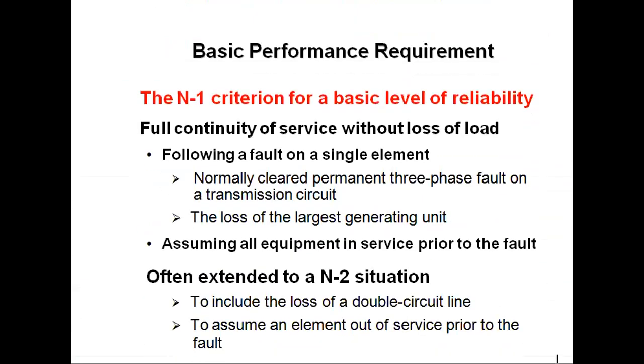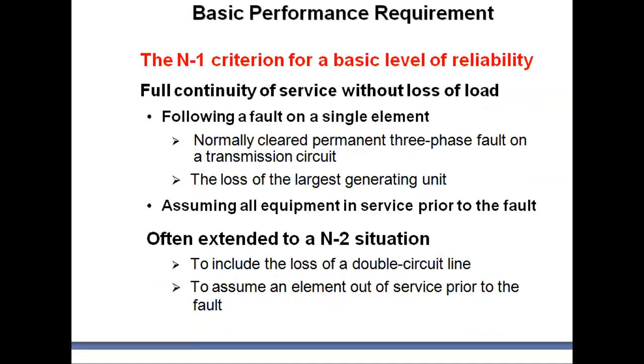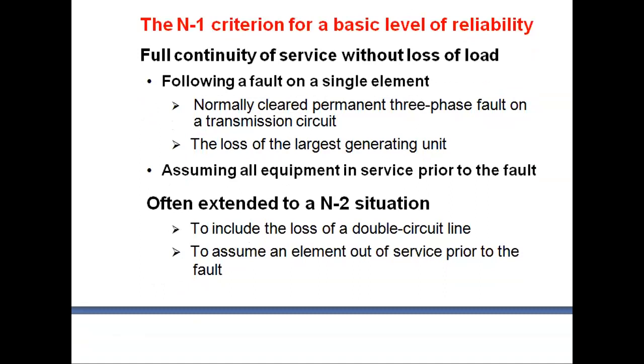The basic performance requirements are classified into two types: N1 and N2 situations. N1 refers to basic level reliability situations and N2 refers to extended ones. For N1: full continuity of service without loss of load, where the fault on a single element can be cleared — normally a cleared permanent three-phase fault on a transmission circuit — and the loss of the largest generating unit, assuming all equipment is in service prior to the fault.